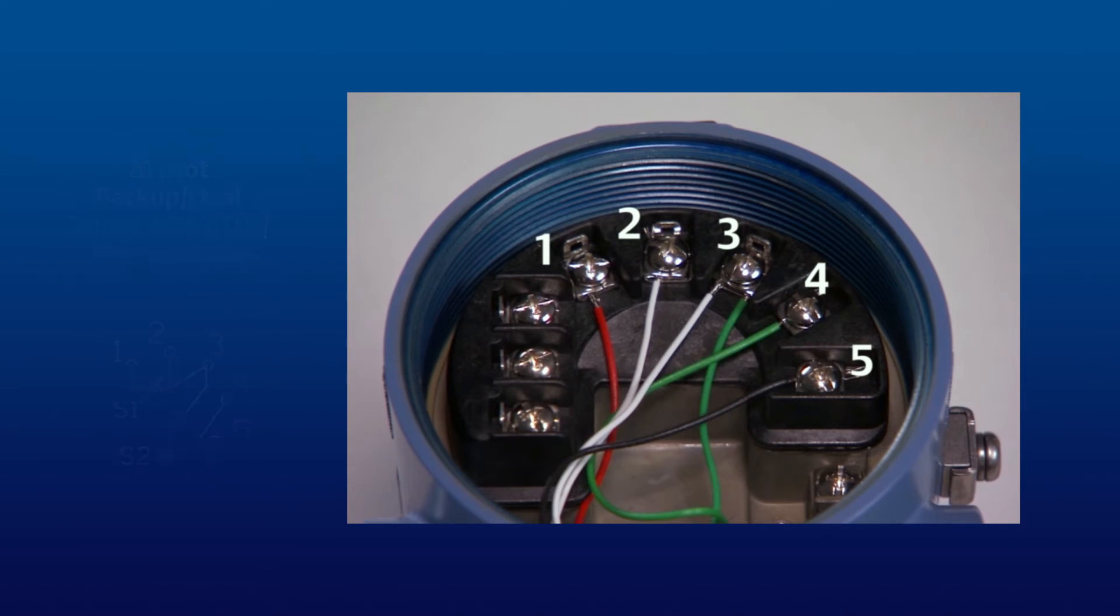Here is the correct wiring when using two 3-wire RTDs. Note that for the first RTD, the single red wire is attached to terminal 1, and the two white wires are connected to terminals 2 and 3.